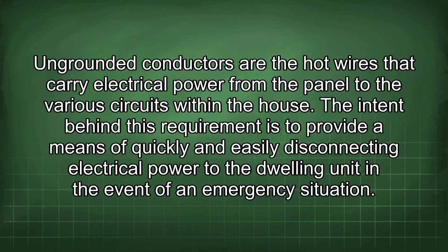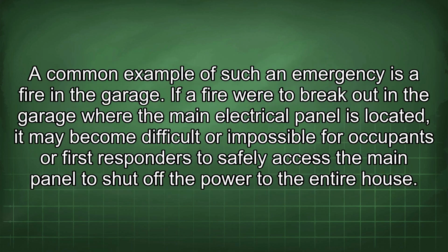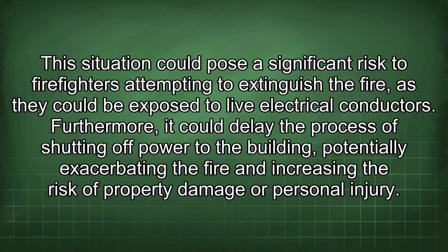The intent behind this requirement is to provide a means of quickly and easily disconnecting electrical power to the dwelling unit in the event of an emergency situation. A common example of such an emergency is a fire in the garage. If a fire were to break out in the garage where the main electrical panel is located, it may become difficult or impossible for occupants or first responders to safely access the main panel to shut off the power to the entire house. This situation could pose a significant risk to firefighters attempting to extinguish the fire, as they could be exposed to live electrical conductors.